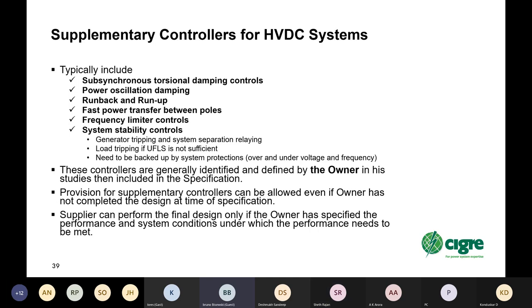Now, supplementary controllers are generally identified and defined by the owner, not the contractor, in his studies, and then included in the specification. You can allow provision for supplementary controllers even if the owner hasn't completed the design at the time of specification. But then you don't get the functional versions of those controls, only, let's say, the skeleton, so you can build a controller later once the studies are complete. And the supplier can't predict what supplementary controls you need. Those are some things that the owner has to specify. And you also need to specify the system conditions under which the performance needs to be met.